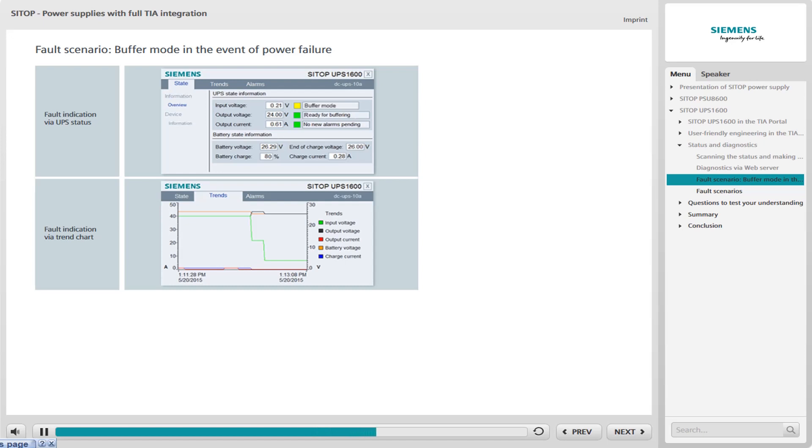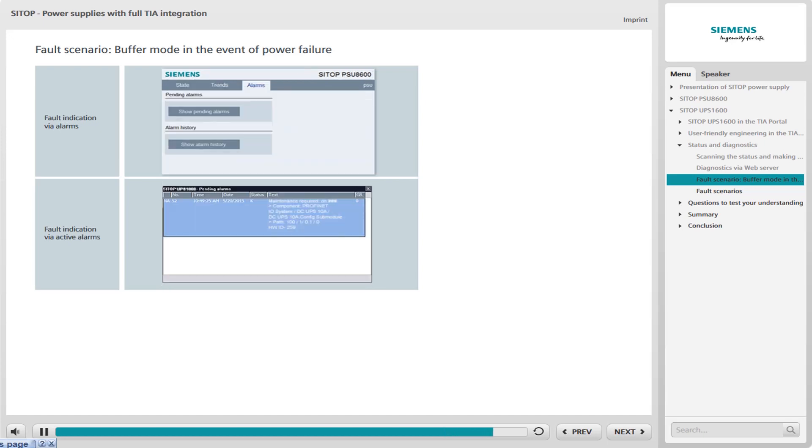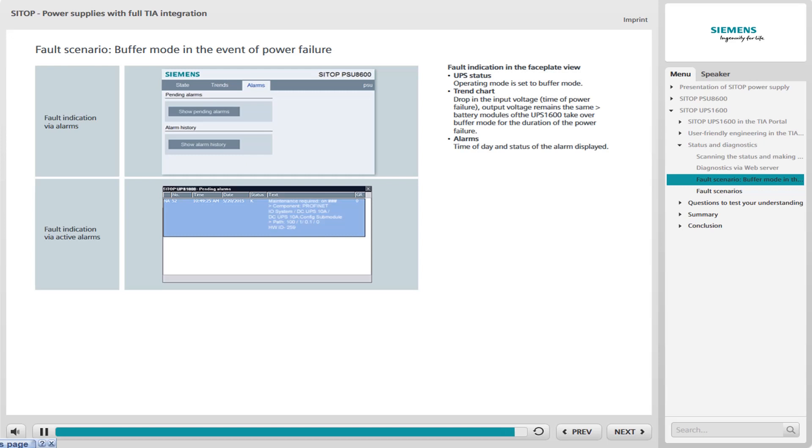However, the output voltage, represented by the black line, remains the same. This shows that the battery modules of the UPS 1600 take over buffer mode for the period of the power failure. Under alarms, you can see the exact time of day and the status.